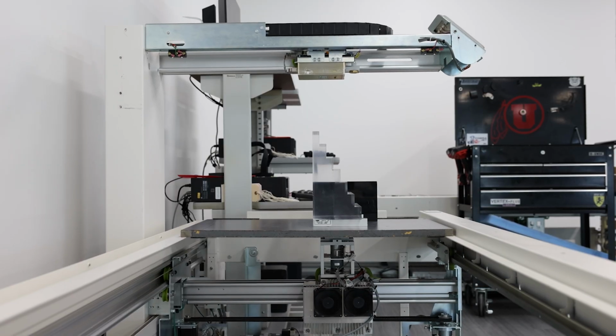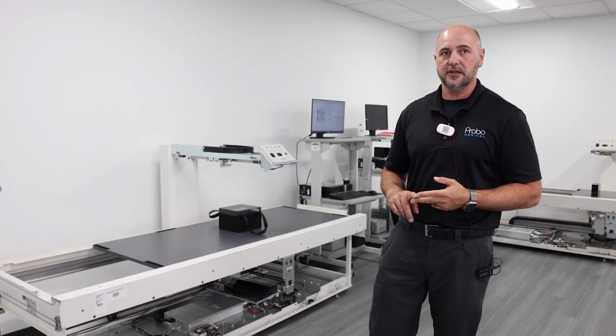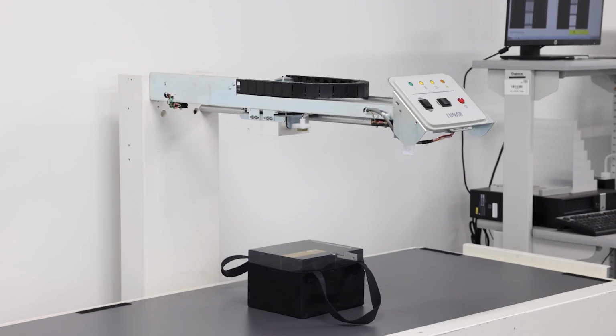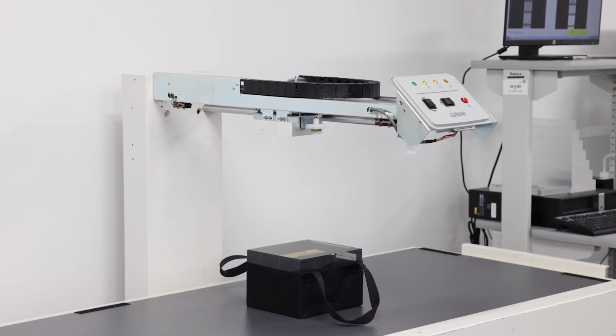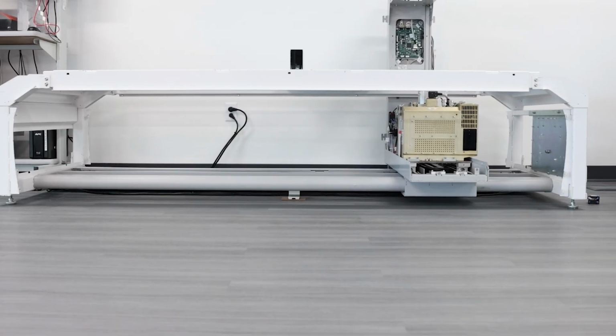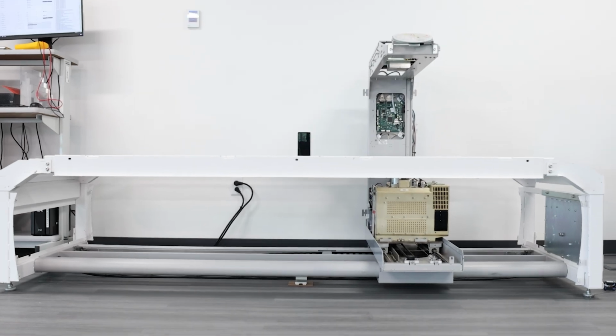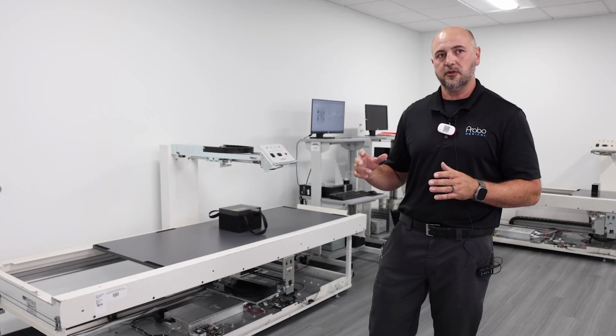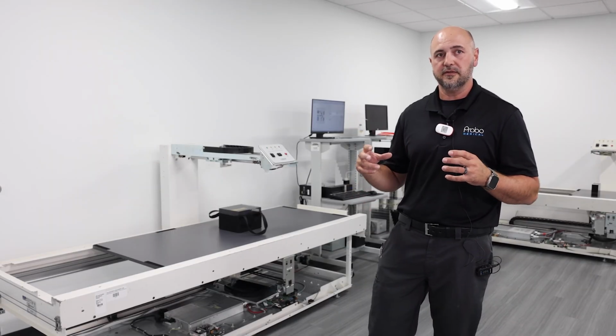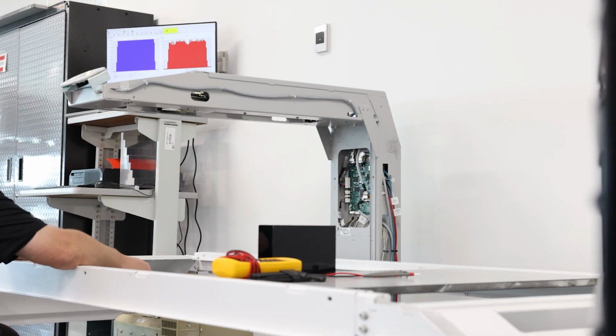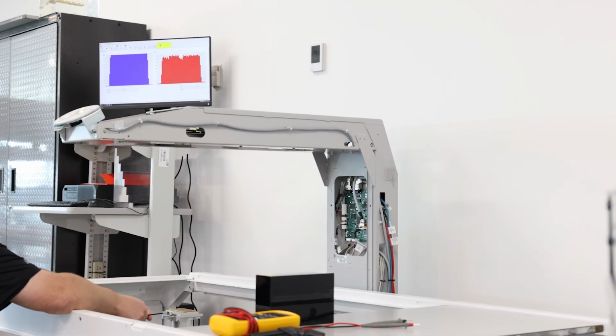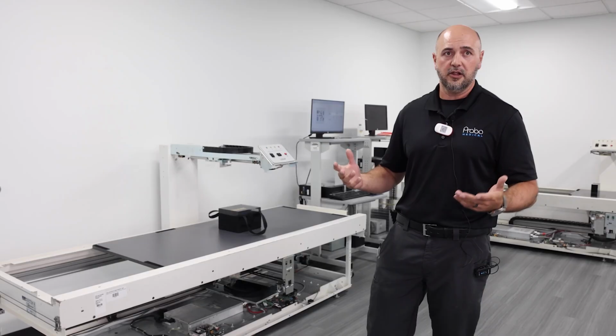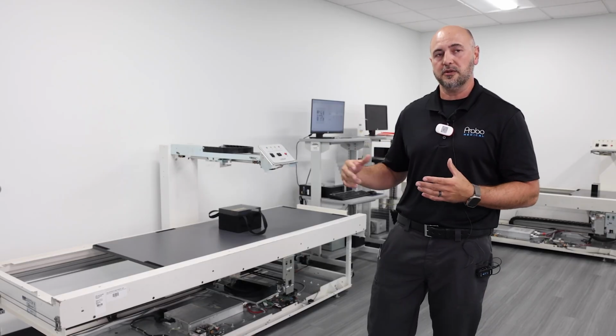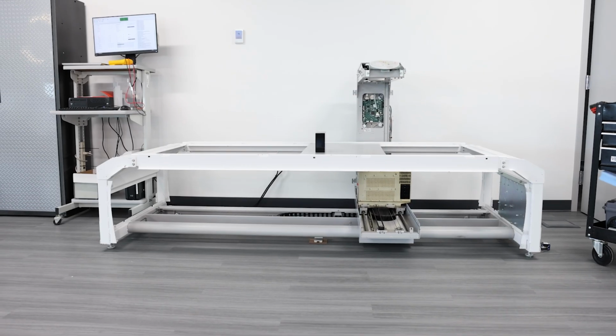Here now, what we'll be testing will be the detector and the tube head itself. What we have placed in the center of the table is a spinal phantom. What we would end up doing is starting a study which would emit X-ray, and depending on that penetration we'll be able to see across the spinal phantom itself what the image quality is actually going to look like as that would go out to the field, therefore qualifying that all of our parts are actually working within the system from all of our repairs.